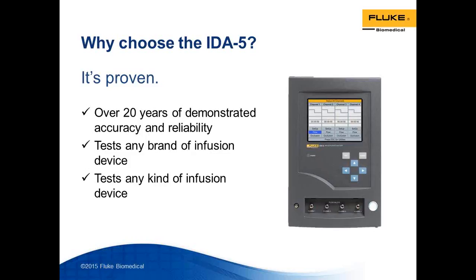Because those characteristics have to be measured manually anyway, you need some kind of mechanism to understand either the delivered volume, the flow rate, or the occlusion pressure. Although Alaris/CareFusion will say that they recommend this technique, the real issue is they cannot recommend a specific analyzer. That doesn't mean you cannot use an IDA-5 or an IDA-1 along with the Alaris software.